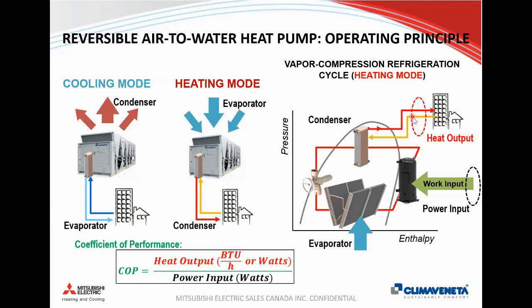Heat pump 101: the coefficient of performance, or COP for short, is the main metric that describes the performance of our refrigeration cycle. It is the ratio of the heat output from the machine divided by the power input. Any kind of heat pump will typically have a COP above 2.